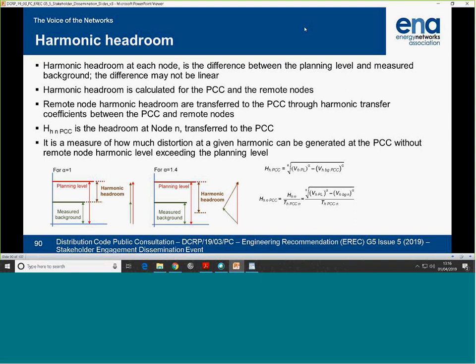Harmonic headroom. We've been talking since morning about harmonic headroom. Basically, harmonic headroom is what is available. Every network has got a background harmonic level, and we have to comply with the planning level. The difference between these two is harmonic headroom. This is what we can use to accommodate a new connection.